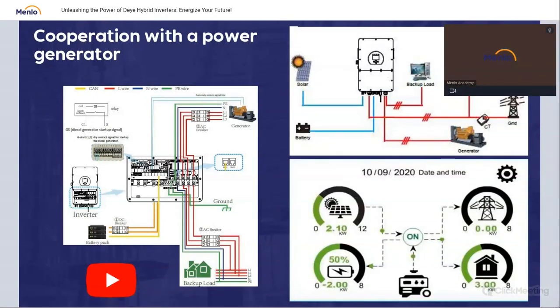Why? Because it has a connected power generator, and you set it like this. As long as you have power from the panels, you charge your batteries and your system is independent. But if during the day there was not enough sun, and during the night the battery discharged and is almost empty, then when it reaches its minimum level, which you as an installer set, let's say 20%, the generator is automatically turned on. You set in the settings what the power of this generator is. It takes the loads, and the rest of the energy from the generator is used to charge the battery.